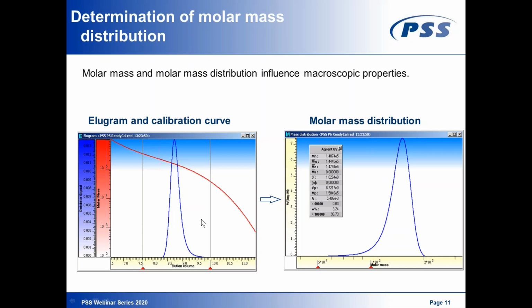Because the chromatogram depends on the resolution of your column. For example, if your column loses resolution, it might be that your peak becomes narrower with time. If you do not monitor that, or if you don't have any idea that the resolution changes, you would think that there are two different samples. And of course, you also cannot compare samples between different labs.